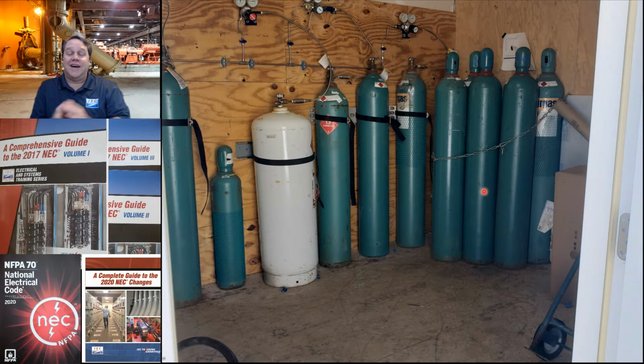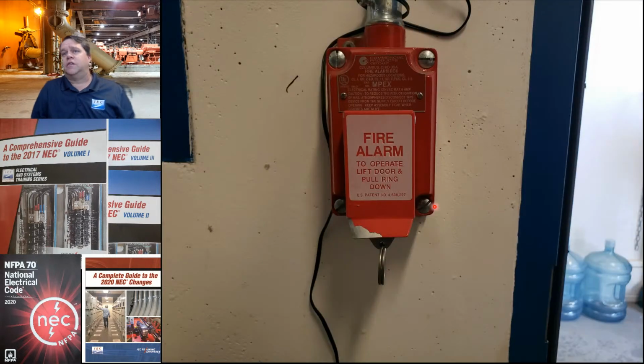It's where they test hazardous locations equipment - a building outside designed to withstand being blown apart. It's pretty small. Out there you've got all sorts of different gases - when testing hazardous locations equipment, you test it with gasoline, butane, ethyl ether, maybe acetylene, whatever gases you need, they have to have on site. What they do when testing this equipment is pretty much pass or fail.